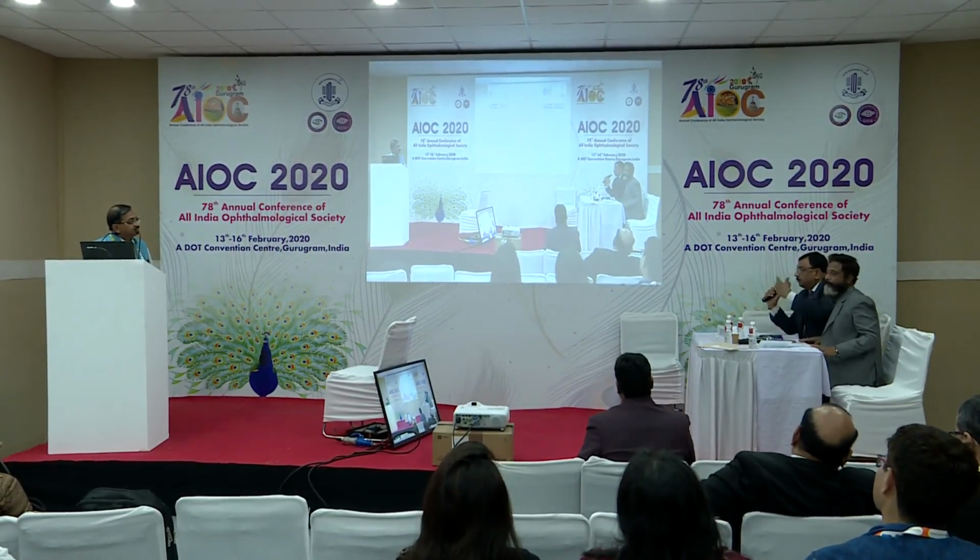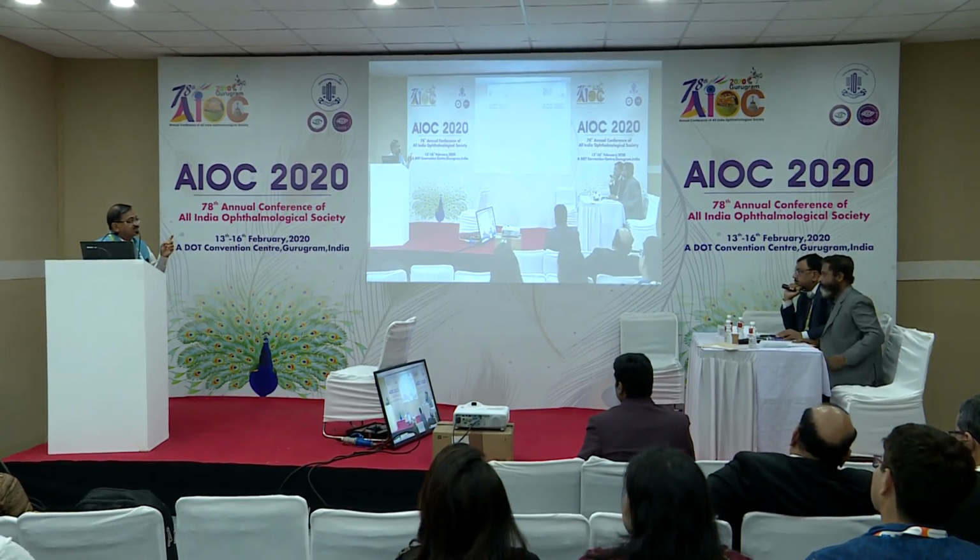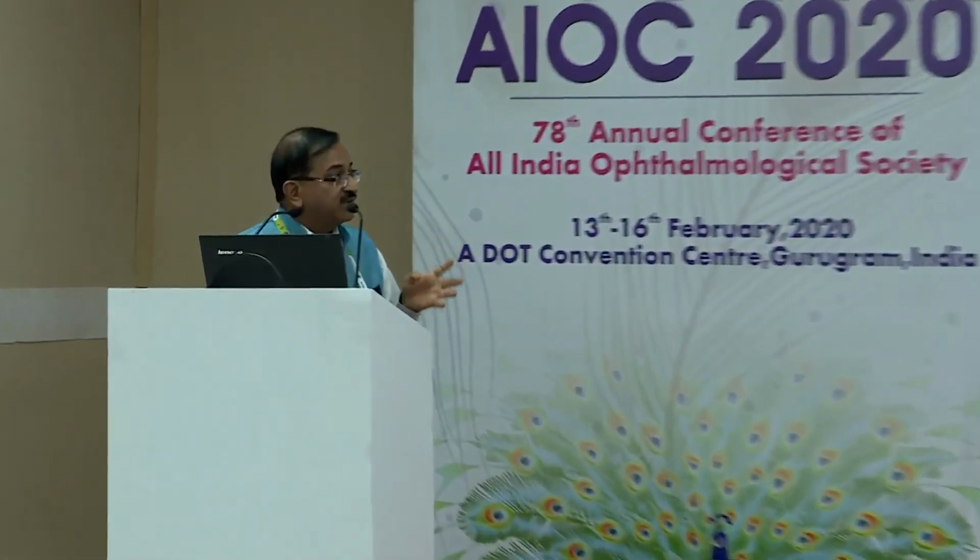Regarding corneal opacity, the thin grade corneal opacity is all right, but what about if... That particular patient had a reasonably, almost a leukomatous opacity. I was myself surprised that it can penetrate. The reason is the longer wavelength of the infrared light doesn't get scattered and it passes through the corneal opacity. We checked that in several patients, but if it is a very dense vascularized opacity, we may not get the pictures. But even leukomatous grade opacities, we get good pictures. Okay, but it's fine till macula grade. But very dense leukomatous, we may not be able to.